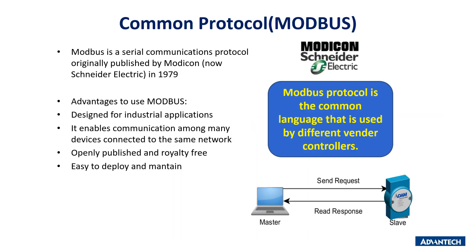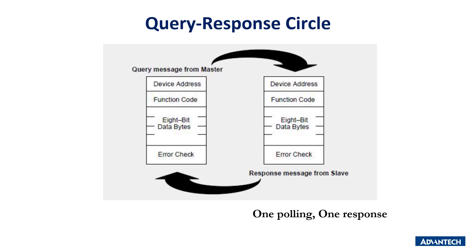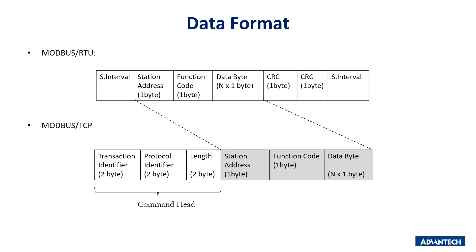Modbus Protocol. Modbus was created by Modicon in 1979 and is used by different vendor controllers worldwide. It is easy to understand, designed for industrial applications, and openly published without any copyright fee. The difficulty of deployment and maintenance of Modbus is relatively lower than other protocols. The basic action is that a master generates a request command and sends it to the slave device through interfaces. If the request is correct, the slave responds with its current status back to the master. This is the comparison table between Modbus RTU and TCP — Modbus RTU has CRC to check commands, but Modbus TCP does not.